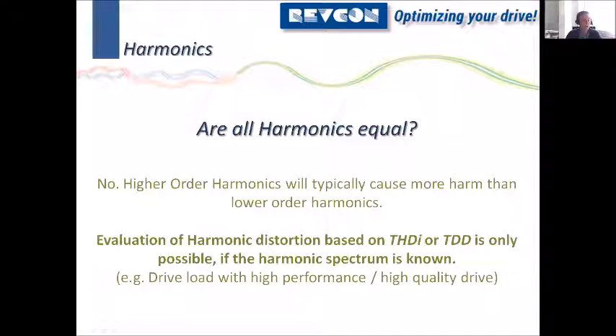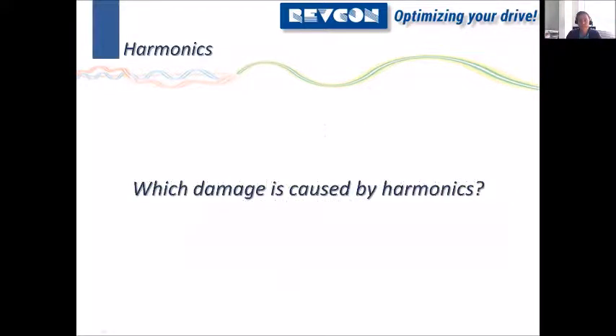So are all harmonics equal? No, they cause more harm when they are higher order. That's just to explain why the THDI is useful, but it doesn't give you the full picture of the situation, because you don't see the spectrum behind the THDI if you only look at the THDI. Unless you really know the spectrum of this drive, you know exactly the spectrum of what it causes, then you can estimate countermeasures against these harmonics. But otherwise, if you are in an unknown situation and don't know anything about the load, the THDI is only a first picture.